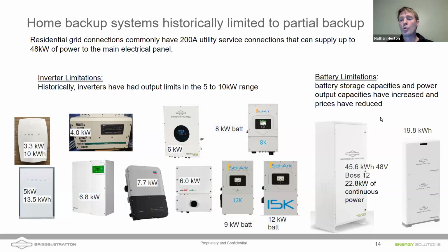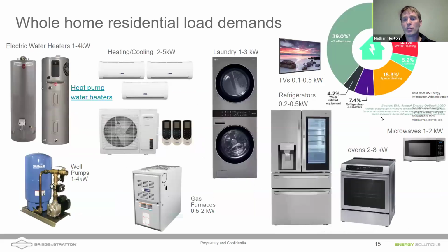And so that goes a long way compared to where we were 5 years ago with batteries. So when we are considering doing whole home backup, we have to consider the loads on the house. If you have a hard start 5-ton AC compressor, you're going to have a hard time running that off of an inverter.